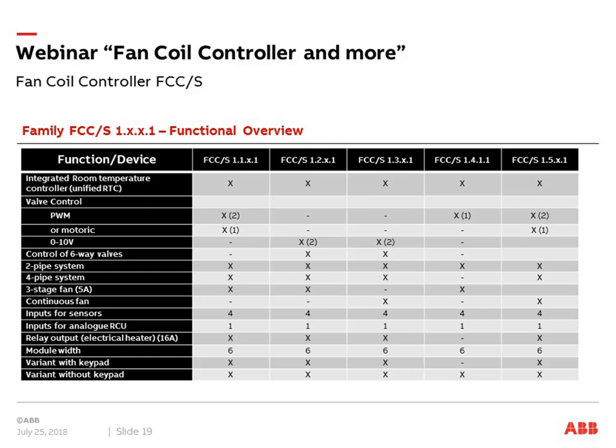This is a summary of all hardware functions across the components. Some have motor or PWM control, some have 0-to-10 volt control. Six-way valve control can only be done with devices that have 0-to-10 volt valve output since an analog signal is required. We distinguish between three-stage fan and continuous control depending on the type. Some components have a keypad for manual operation and some do not.